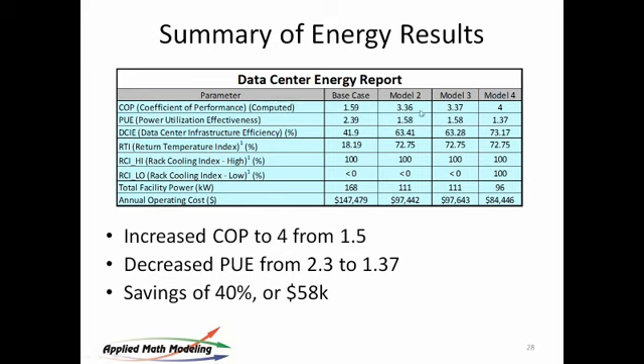So here's our summary. We went from 1.59, or PUE of over 2, down to 1.37. We went from a cost estimate of 147 to 84. That's a $58,000 delta. And as I said earlier, users may not feel comfortable predicting the actual cost of operation. They may want to use percentages and say, Mr. Customer or Mr. Operator, I think I can save you 40% by doing these changes. So on a budget of $150,000, 40%, you can do your own ROI. It happens quick. And all we did here was switch things off. Now, we probably also put backflow preventers in place, but that's just sheet metal, louvers, not complicated, not expensive. And also here we put some curtains in place, which aren't expensive either.